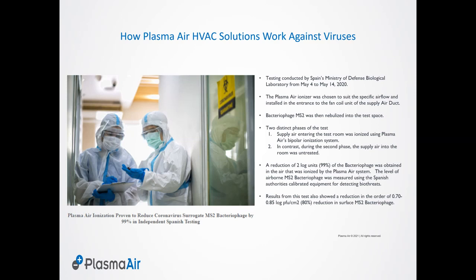And the bottom two bullets are the result of that. There was a 2-log reduction, 99%, in 10 minutes of the MS2 bacteriophage, which has been previously mentioned. So that's a good result. In 10 minutes, you're getting excellent reduction. Not only that, not only airborne, bipolar ionization typically isn't regarded as a surface technology, and I don't want to claim that it's a surface technology, but there was an 80% reduction in surface contamination, and that's really due to the fact that when the positive and negative ions are in this space and the chemical reactions are taking place, what falls out of the breathing zone, if it's heavy enough to fall out through agglomeration, are non-toxic particles. So it was a good result, primarily for airborne, but certainly surface as well.